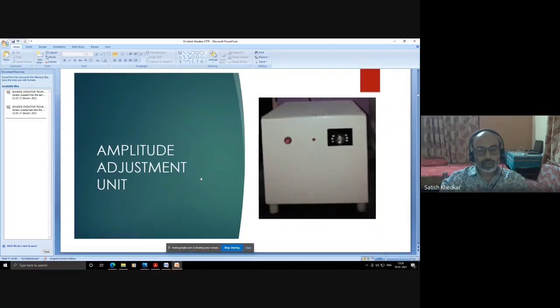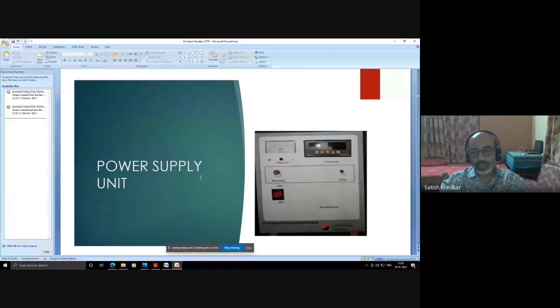Then the second component of the system is the power supply unit. The power supply unit is also responsible for giving you the idea about the load being exerted on the machine due to the cavitation process. Now the load can be seen in the left part of the picture where a pointer is there. The pointer is shown there. The pointer shows the load on the sonication probe, and it is directly proportional to the viscosity of the liquid which is being sonicated. For low viscosity liquids, the load will be much lower. For high viscosity liquids, the load will be much higher.